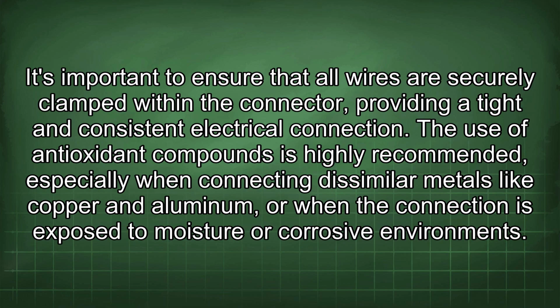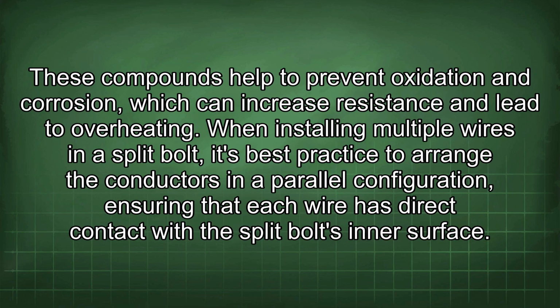The use of antioxidant compounds is highly recommended, especially when connecting dissimilar metals like copper and aluminum, or when the connection is exposed to moisture or corrosive environments. These compounds help to prevent oxidation and corrosion, which can increase resistance and lead to overheating.